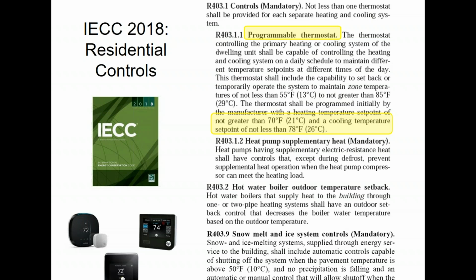Snow melt systems, you cannot have your snow melt system or ice melt system running wild. These have to be controlled. Specifically, it details what you have to do here. You have to be able to shut off the system when the pavement is above 50 degrees. So when you're installing this, you've got to put a pavement sensor in.